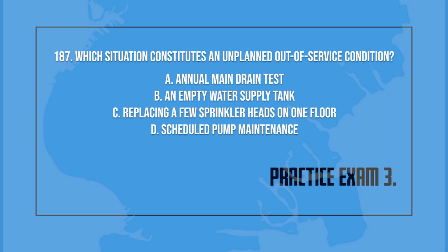(187) Which situation constitutes an unplanned out-of-service condition? A. Annual main drain test. B. An empty water supply tank. C. Replacing a few sprinkler heads on one floor. D. Scheduled pump maintenance.